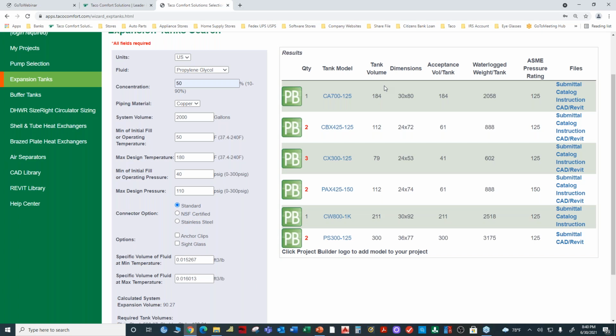It was only 119 gallons. And so the pressure inside the tank at 119 gallons is going to exceed 110 PSIG. And if that happens, the safety relief valve perhaps could go off and you could have water and glycol all over your mechanical room. This is not a good day. So that's one of the things that we see occasionally.